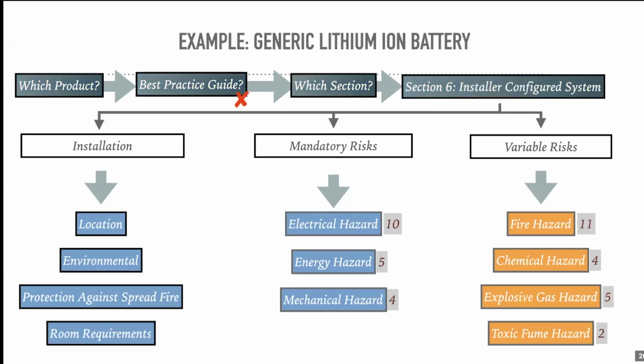But it's when you get to section 6, which is anything that is not lithium, and anything that is lithium but not compliant with the best practice guide falls into this. And now you've got a very large number of mandatory risks and variable risks to assess. Now I should point out, how do you make these assessments? The standard actually requires a risk assessment as a shall when installing a battery system or a BESS. And so there's a sample risk assessment within the standard. I mean, sometimes standards actually hold your hands. They provide you with examples and charts and tables, etc., that you can use, maintenance schedules, those sort of things.